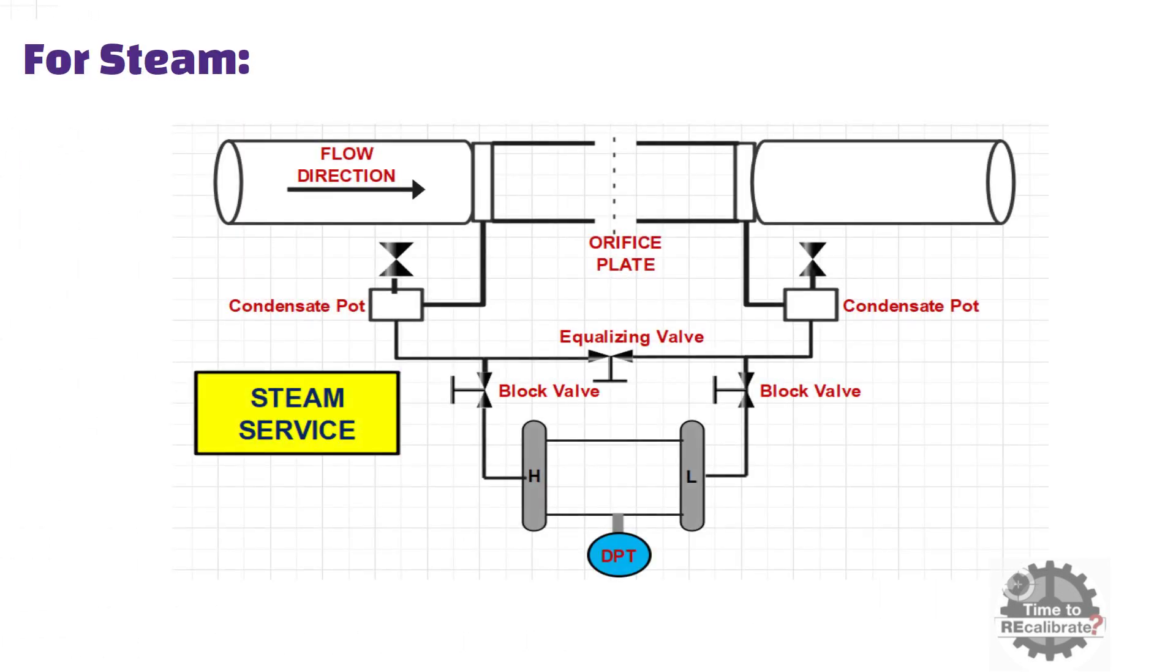For steam lines, DP transmitter should be installed below the orifice plate with condensate pots. And also make sure that the pots should be installed at same level.